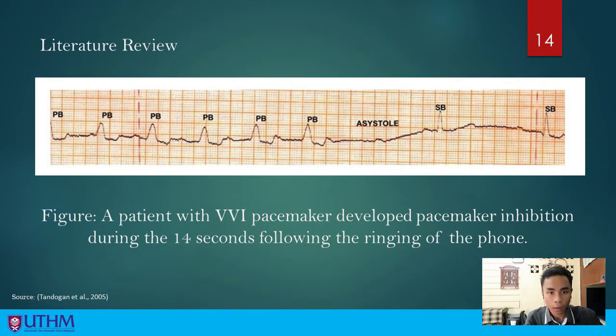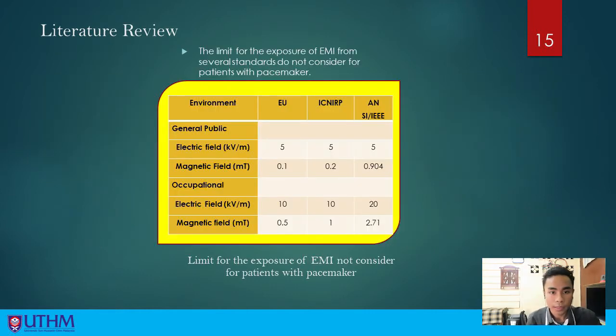The condition here is a patient with VVI program setting who developed pacemaker inhibition during the 14 seconds following the ringing of the phone. Here is the limit standard for the exposure of EMI from several standards such as ICNIRP, but this standard limit does not consider patients with implanted medical devices such as pacemakers, since the interferences can arise because of both magnetic field and electric field through the induced voltage in the leads between the device and the electrode of the heart. The sensitivity setting of the pacemaker is important to know the immunity of the pacemaker from interference.